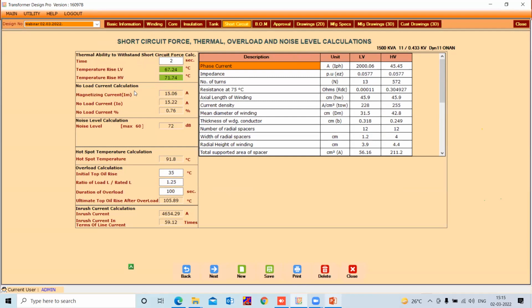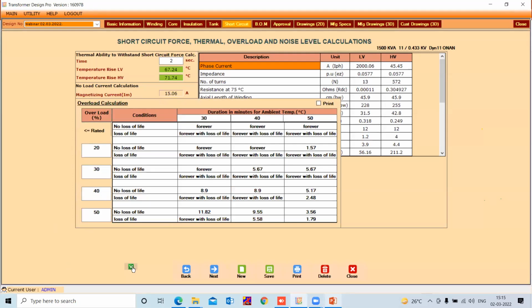Thereafter, the no load current calculation. In that, you'll get the magnetizing current and no load current in ampere as well as in percentage. Thereafter, the noise level calculation. Then hotspot temperature calculation, overload calculation, inrush current calculation. And there is a button for loss of life calculation for different kinds of overloads and temperature conditions.